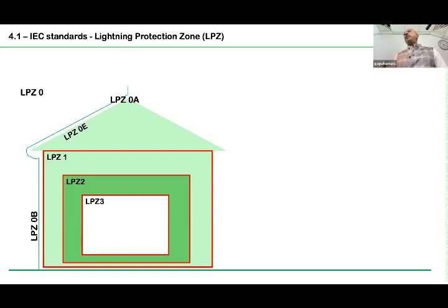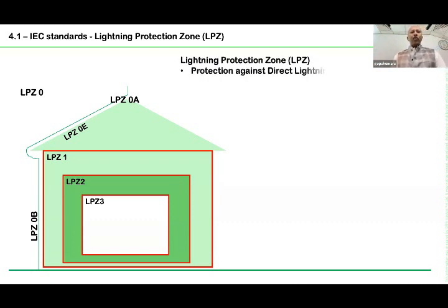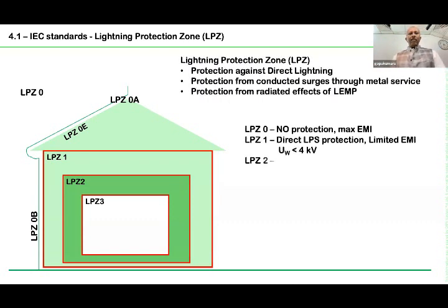Now, one of the principles used in the IEC standards, not only for surge protection but for all EMI/EMC radiated protection, is zoning of the building. The building is divided into various zones with respect to lightning protection zone 1, 2, 3. Zone 1 means the conducted surges are limited to less than 4 kV. Zone 2 means less than 2.5 kV. Those classifications are there, but I don't want to go into it because sometimes it confuses.